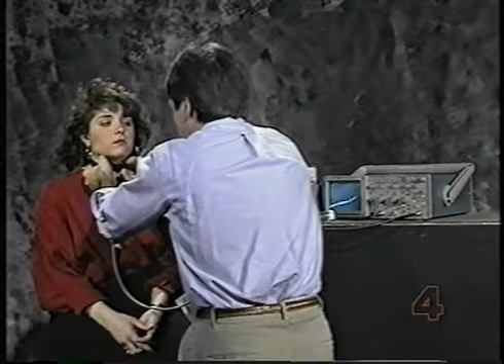Could you say ah? Ah. Okay. I'm moving the electrodes up and down a bit until I get a good strong signal. Try it once more. Once more. That's good. EGG signal strength is monitored on the meter of the device, and I can also use an oscilloscope to determine the position that yields the greatest output signal.